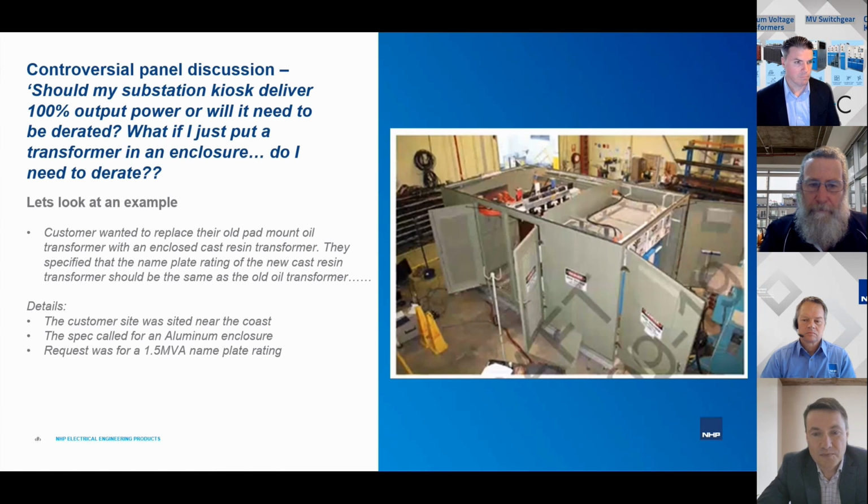Eventually, we decided to run a type test, which became very useful for us for future reference in our designs of kiosk substations. The type test, by the way, was performed at the Lane Cove test laboratory in Sydney, which used to be our major test laboratory for all MV and HV tests in Australia, and unfortunately has been closed just recently. But we were still lucky to have the chance to do this type test quite a few years back.